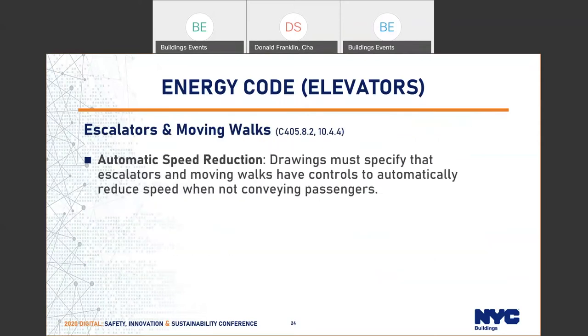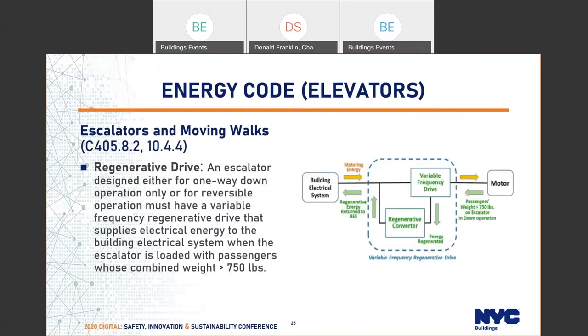For escalators and moving walks, they are required to have controls that reduce speed when they're not conveying passengers. For escalators going one way or down, when carrying combined passenger weight of 750 pounds or more, they are required to have a regenerative drive which feeds energy back into the electrical system of the building.